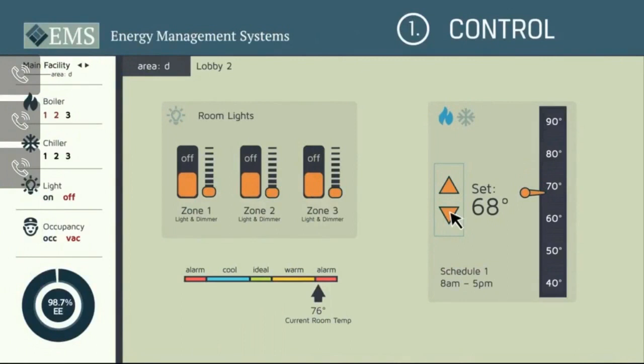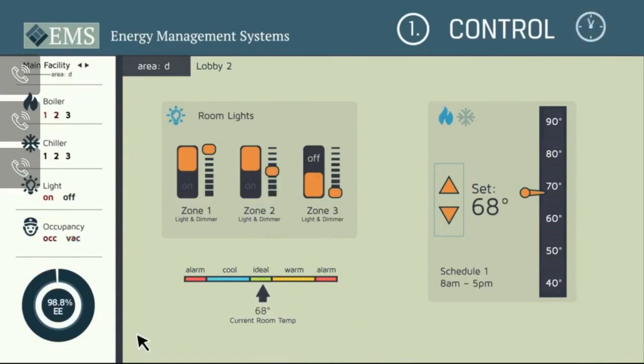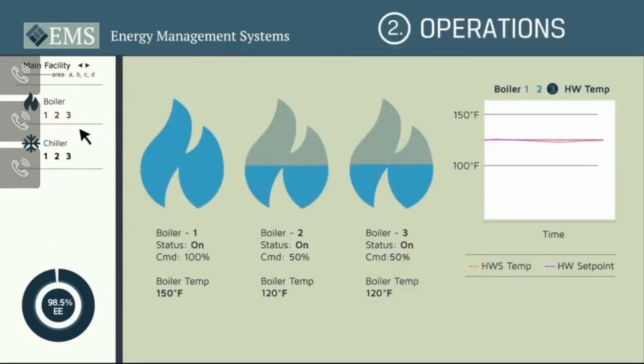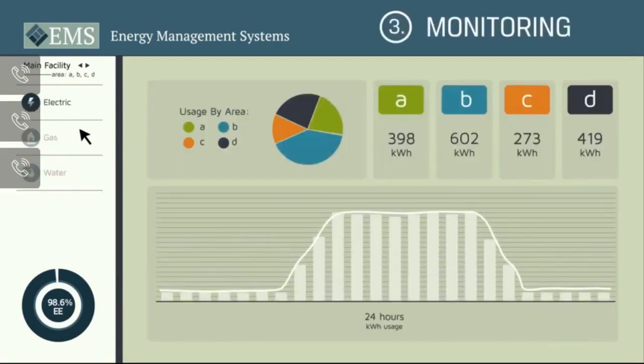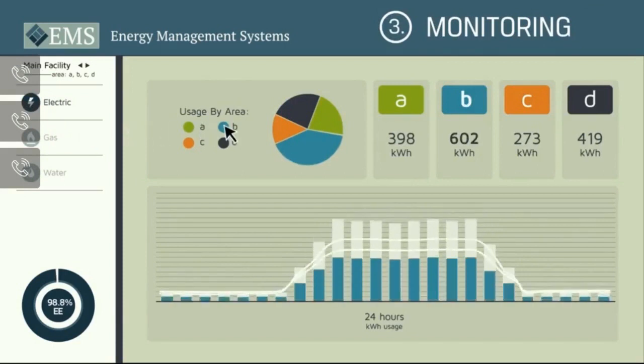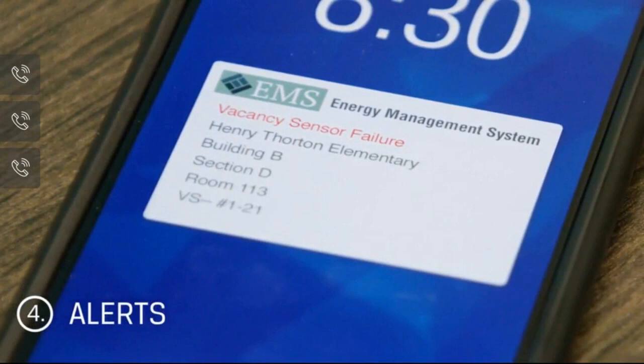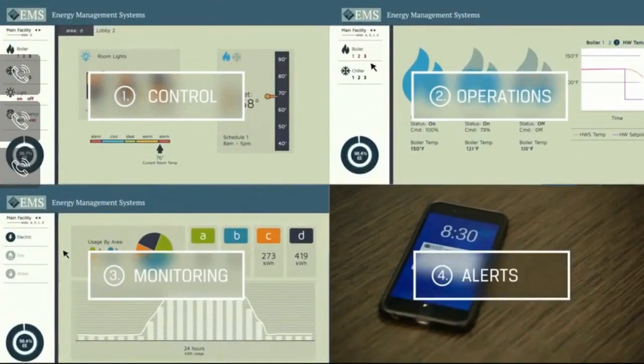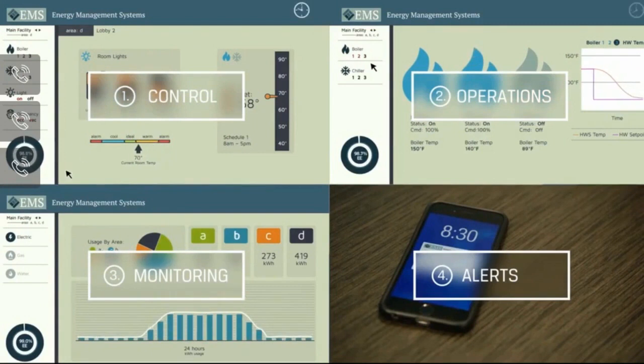An energy management system can help save you money by performing 4 basic functions that translate across a variety of applications. First, it controls the building environment. Simply put, an EMS delivers just the right amount of conditioned air, fresh air, and lighting specifically tailored for each type of space in your building, always with an eye toward energy savings. An EMS will operate your building functions based on a prescribed sequence of operations and control strategies, reacting accordingly when specific conditions, like occupancy or daylight, change. By monitoring performance, an EMS can even implement corrective actions, and you can see it all on the dashboard so you know what's happening in your facility at all times. An EMS will also send you alarms and alerts that let you know if something needs attention. An energy management system provides control, operation, monitoring, and alerting, improving efficiency, lowering maintenance costs, increasing productivity, and enhancing safety in your facility.